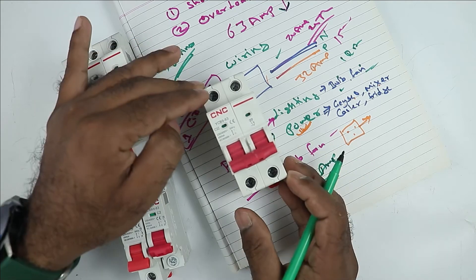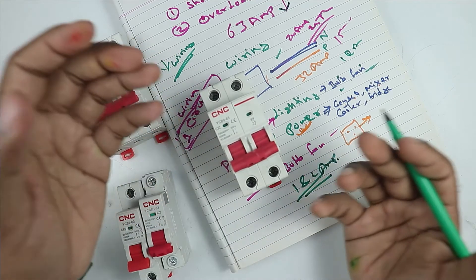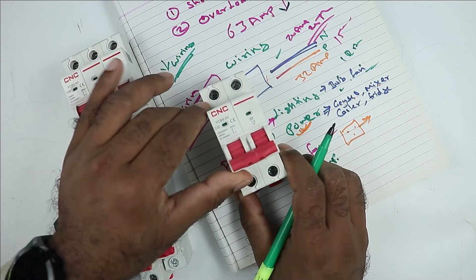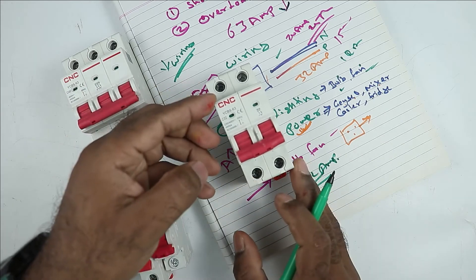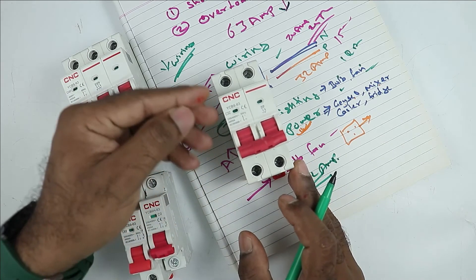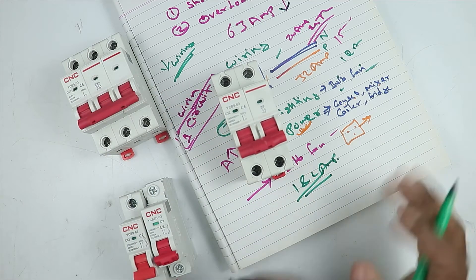For only 1 to 2 ampere current, if you install the MCB of 32 ampere, then how you are going to get protection? Your MCB will not trip till the current flowing through the MCB goes beyond 32 ampere.